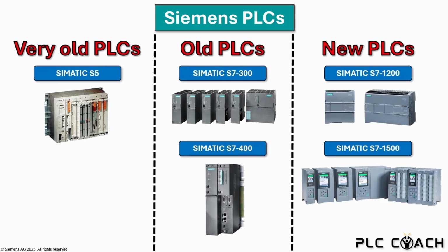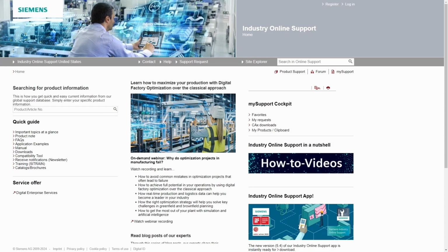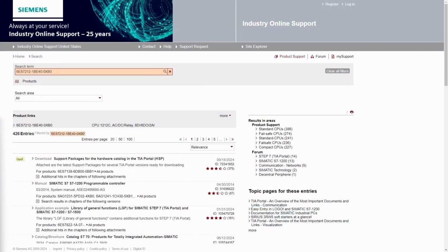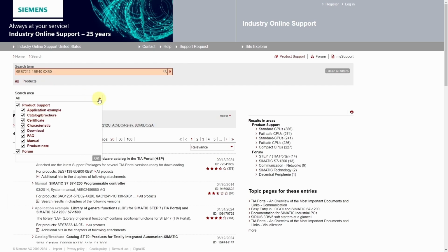And now, at the end of the video, comes the most important advice I can give you as a PLC programmer. The most important advice is, be like this worm. Before you start working with new PLC hardware, read the funny manual. Trust me, in the manual you find everything you need to know. If you want to work with Siemens PLCs, you should always have the manual available on your computer. Below the video you will find the link to the Siemens Industry Online Support. If you're looking for the manual for a specific device, simply enter the article number in the search bar. Then filter the results by manuals and select the latest version.